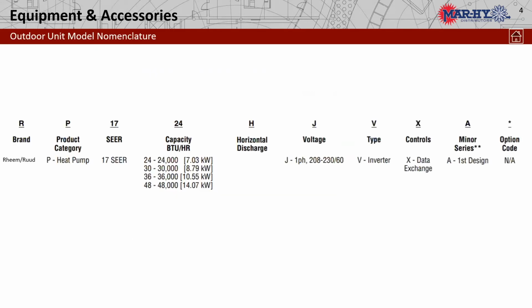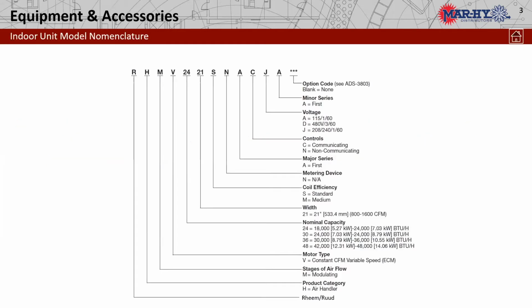For the outdoor unit, RP17, the only thing that's going to look different here will be the H. The H will tell us that that is a horizontal discharge. The V tells us that it's an inverter, and the X tells us it's a data exchange control wire. So there again, be specific on your air handlers. The first few letters and numbers look very similar to what we would have with our 20 SEER air handler, but there again, this is specific to the 17.